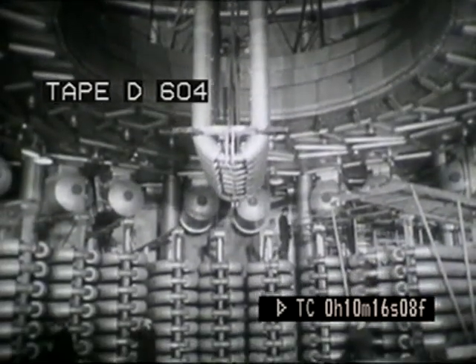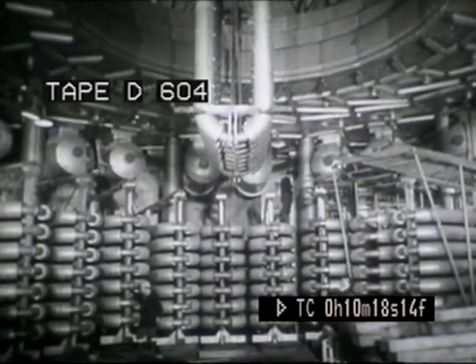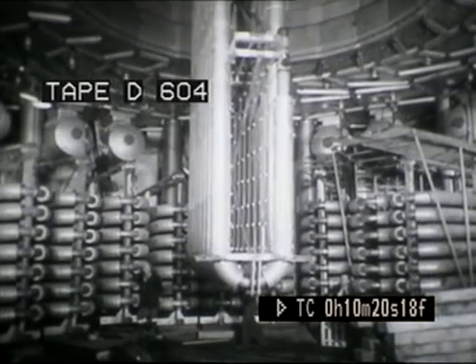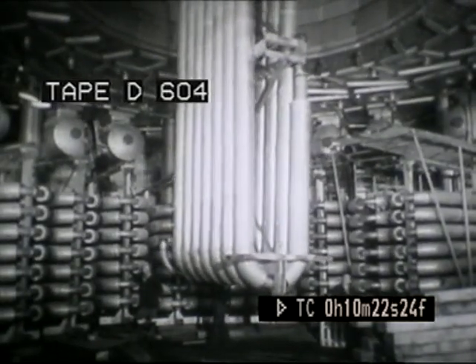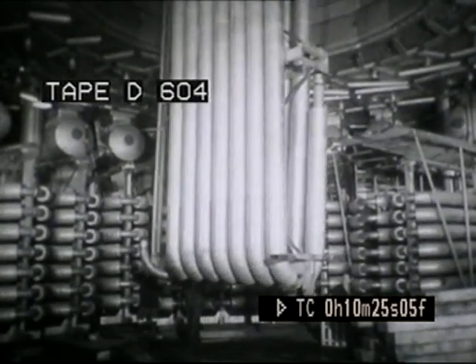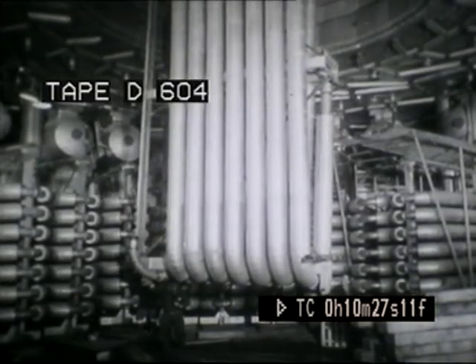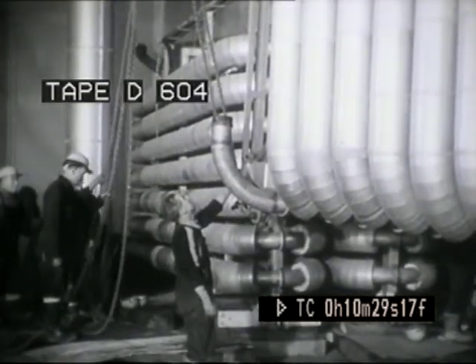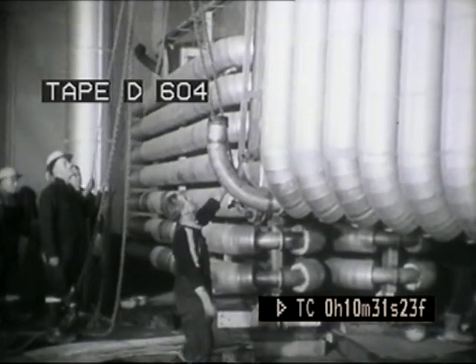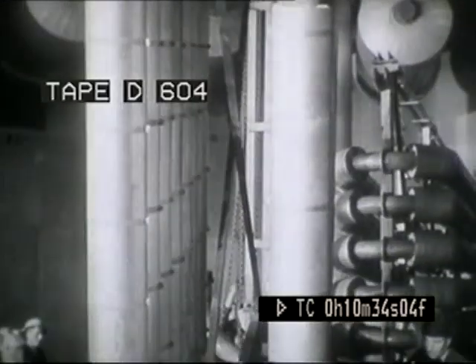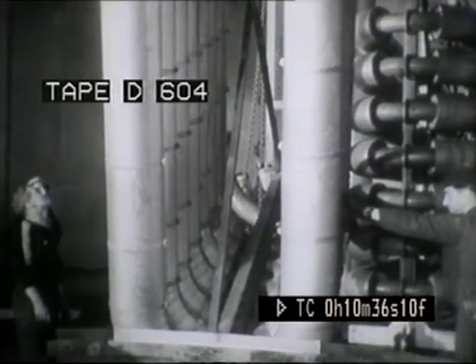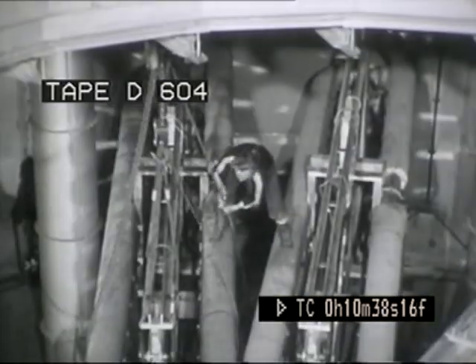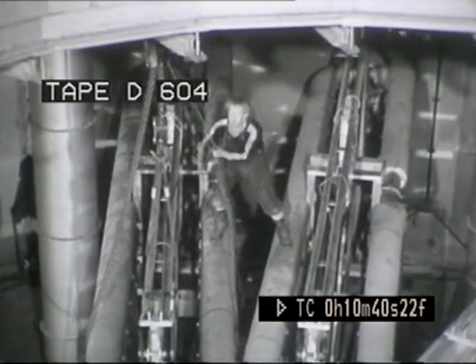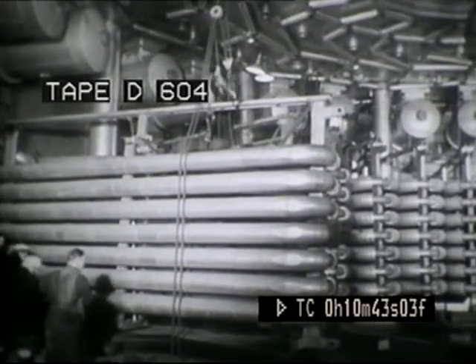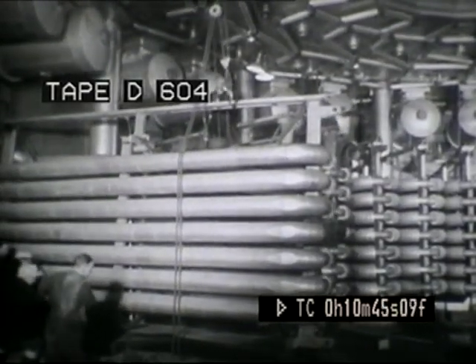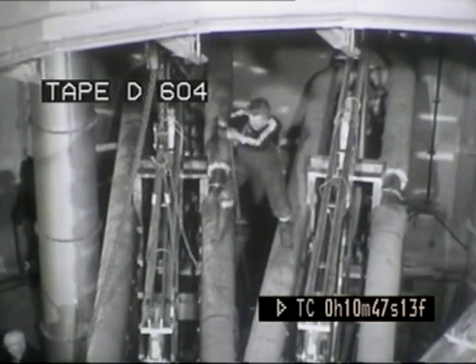Space within the vault was at a premium. Once the reactor vessel was in position, it would not be possible to insert any further components of any size. Erection planning was therefore a major operation. It was necessary to store for later use some 2,000 sections of pipework in the vault before the vessel was brought in. Later, the heat exchanger units would be hoisted up and slung into their final position a few feet below the vault roof, and the sections of pipework would be used to connect them with the electromagnetic pumps and the vessel.